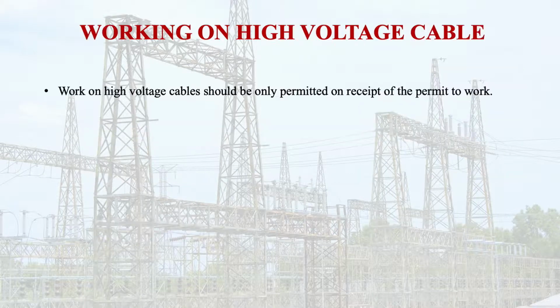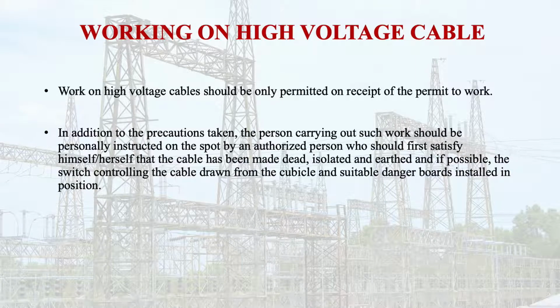Working on high voltage cable. Work on high voltage cable should only be permitted on receipt of a permit to work. In addition to the precautions taken, the person carrying out such work should be personally instructed on the spot by the authorized person, who should first satisfy himself or herself that the cable has been made dead, isolated and earthed, and if possible the switch controlling the cable drawn from the cubicle, and suitable danger boards installed in position.